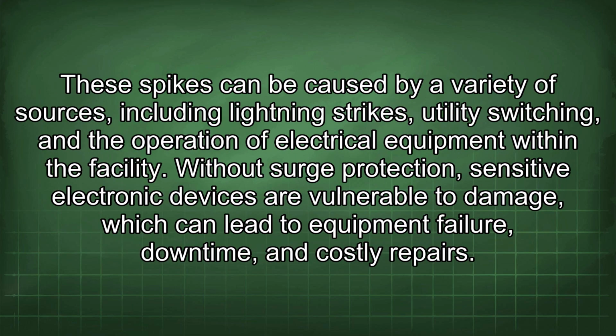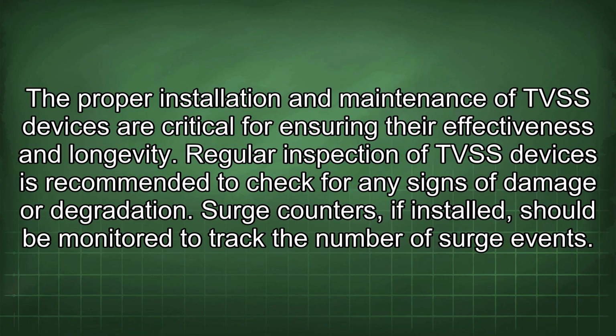These spikes can be caused by a variety of sources, including lightning strikes, utility switching, and the operation of electrical equipment within the facility. Without surge protection, sensitive electronic devices are vulnerable to damage, which can lead to equipment failure, downtime, and costly repairs. The proper installation and maintenance of TVSS devices are critical for ensuring their effectiveness and longevity. Regular inspection of TVSS devices is recommended to check for any signs of damage or degradation.